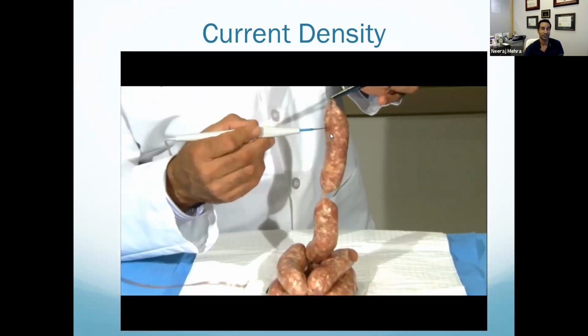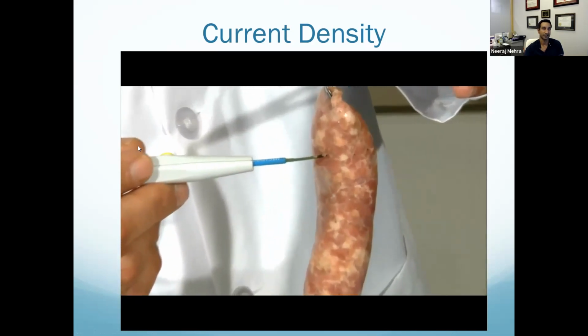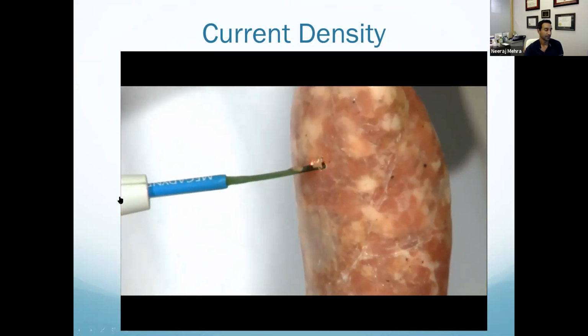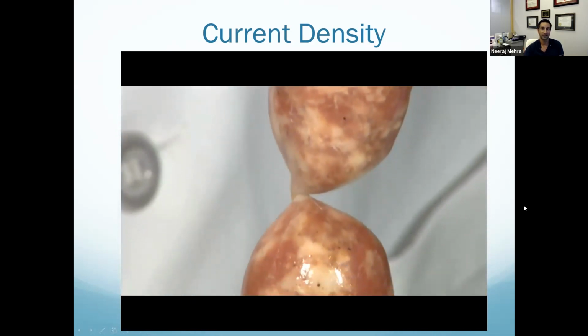So again, I don't know if it's something that's actually been documented as happening, but it's something to be aware of because it certainly could happen or cause some sort of injury that you may not actually know about, because there could be a problem and no one can understand why it happened, and you can't really look back in retrospect and figure it out. But it definitely has the potential of happening, especially if you're using a lot of energy, and especially if you, so here you can see he's using the coag mode also, right? The coag mode is generating high voltages, and those high voltages are going through the patient, through that area of high current density.